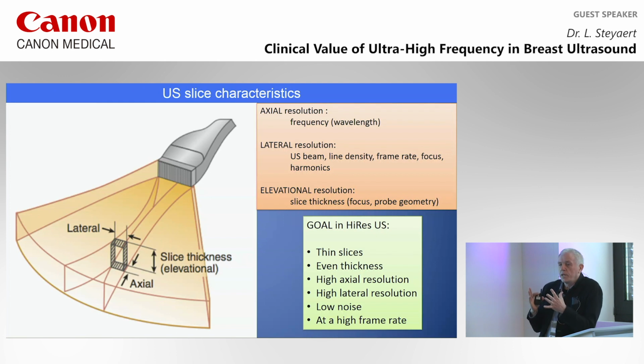If you look at an ultrasound image, it's a slice, and the slice has a certain thickness and certain characteristics. You have the axial resolution. Axial resolution is mainly dictated by the frequency. So the higher the frequency, the smaller the wavelength, the better your resolution. So that's an improvement of the ultra-high frequencies. The second thing is the lateral resolution, depending on a lot of things, also on the probe and on the technology behind. But you also have a third factor, the slice thickness or the elevational resolution, and that's very important. It depends on the probe technology and also on the construction of the probe and the machine.